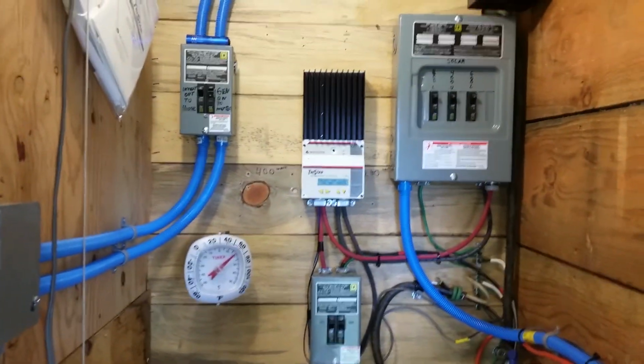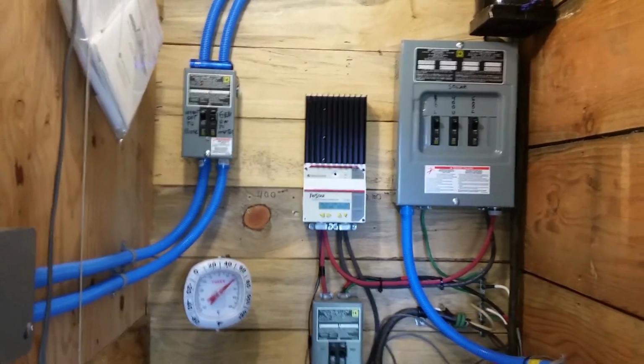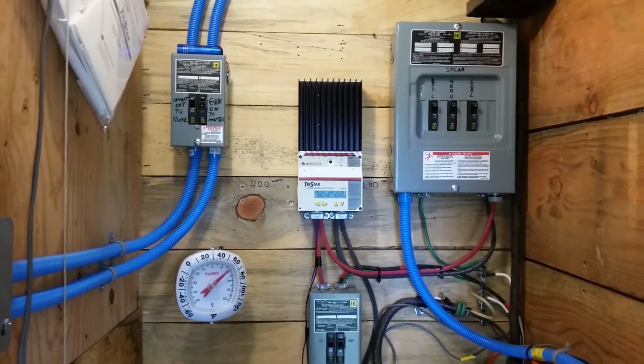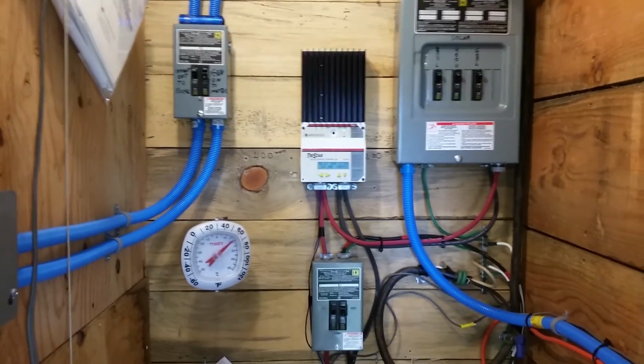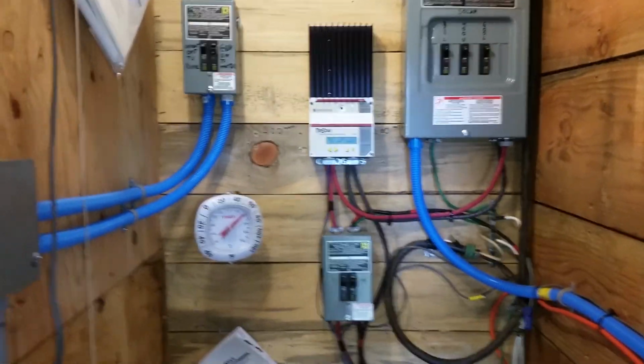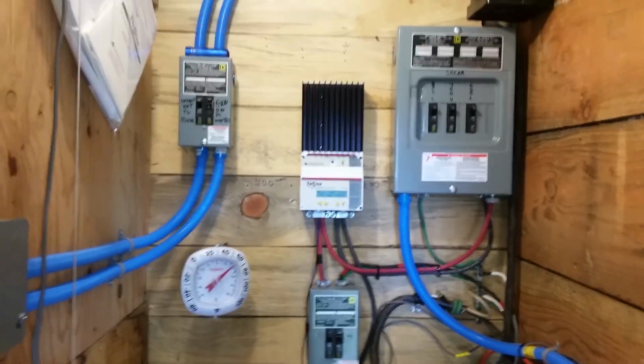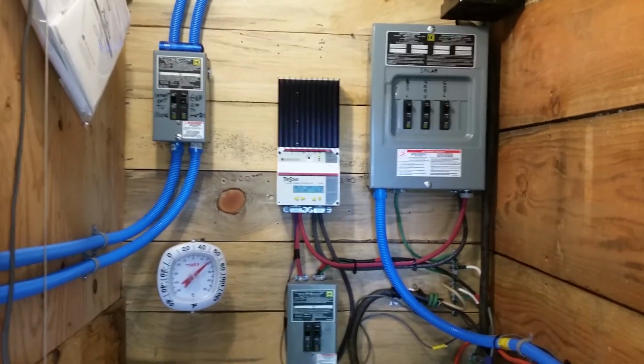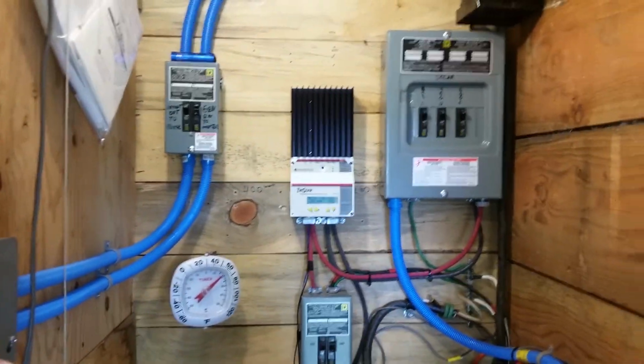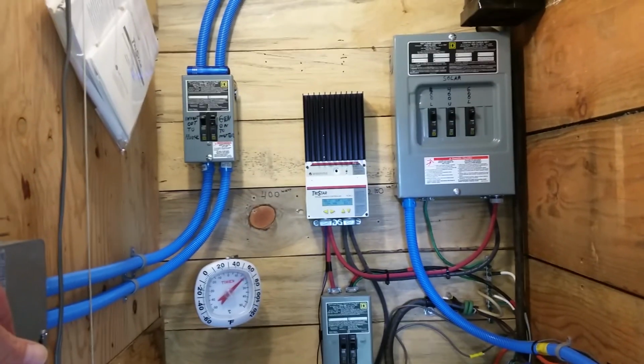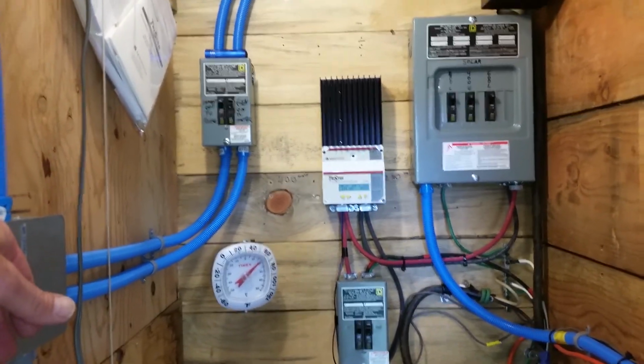So if you're experimenting and you've got a shed and you're learning about it, don't cut corners. Even if it's in a shed and not connected to the house, use fuses, the right kind of fuses. AC fuses will not work on a DC system; they need to be DC rated fuses, and the breakers need to be DC breakers in the right application.